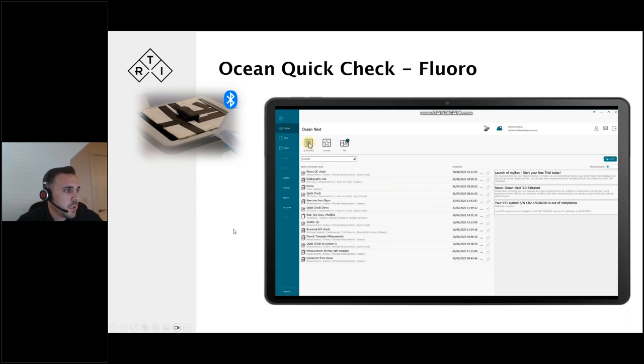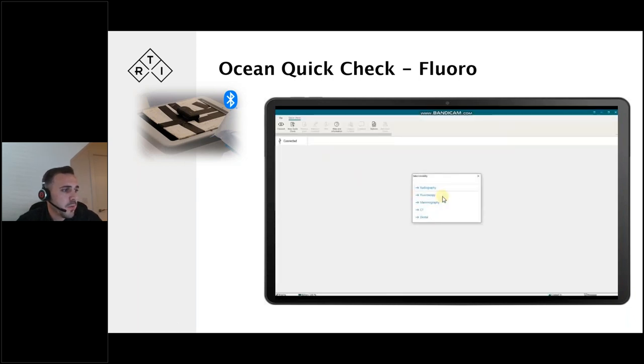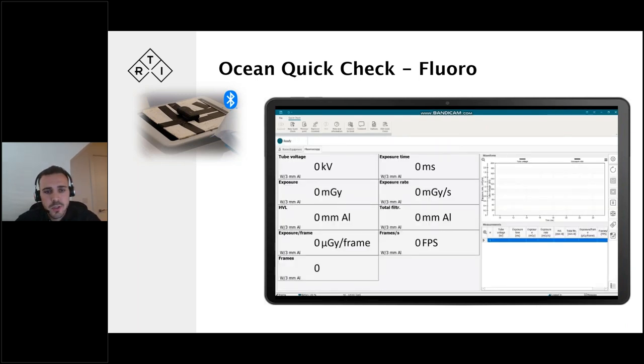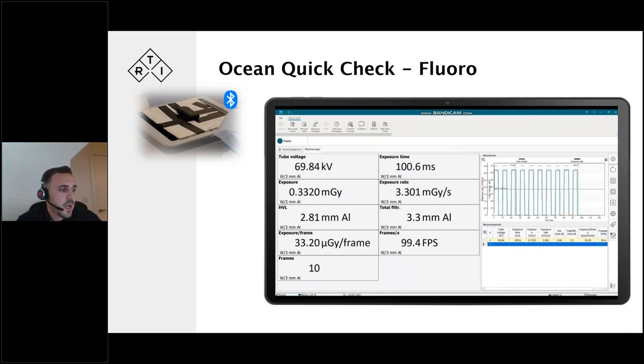If we went into Quick Check, and this time select fluoroscopy, which is pulsed radiation, you'll see that the software again auto-configures to that modality, so that now we have a couple of extra measurement parameters, such as the number of frames in the exposure, the frames per second, and the exposure per frame.